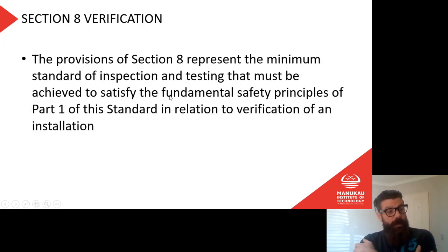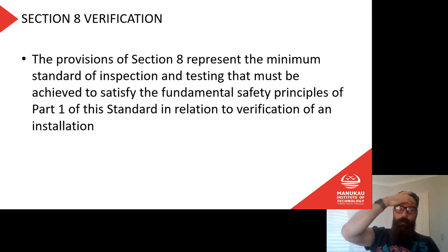Section 8, verification. So this is probably for us, at least in our initial stages, the most important one. Section 8 gives us the standards for inspection and testing that must be achieved to satisfy the fundamental safety principles of part 1, and so on and so forth. So when we've completed building our installation, this tells us how to do the inspection and testing, section 8.